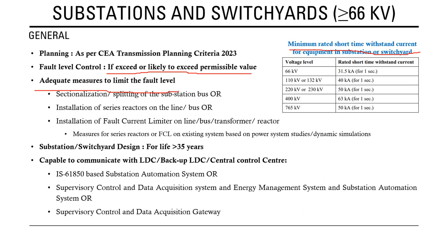The design life of substations and switchyards should not be less than 35 years. The substation should be capable of communicating with the load dispatch center, backup load dispatch center, control center, ISOs, and ASOs. It should be an IEC 61850-based Substation Automation System, or SCADA and EMS system, or a combination of both, with a substation supervisory control and data acquisition gateway for communication with different control centers.